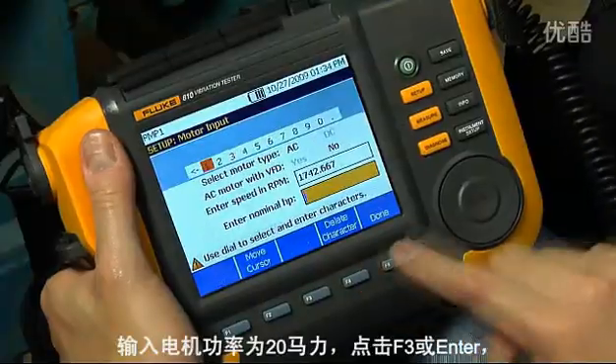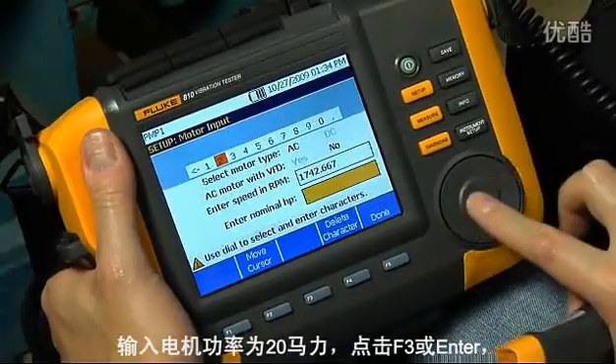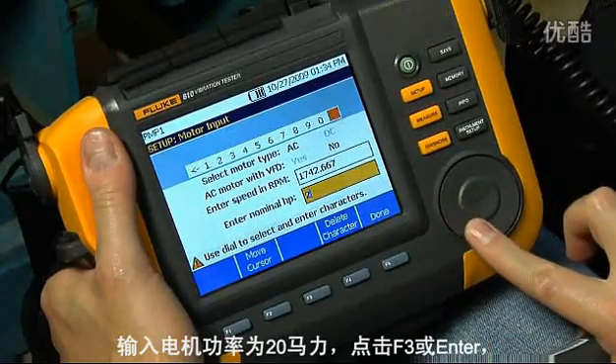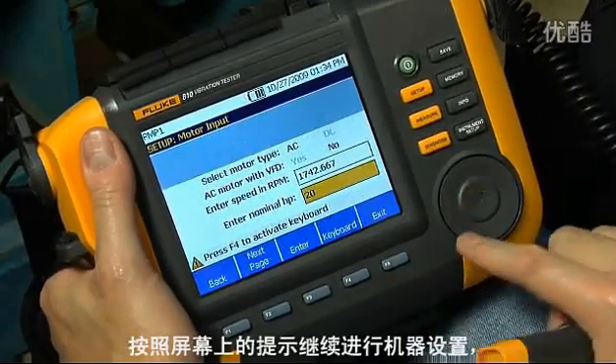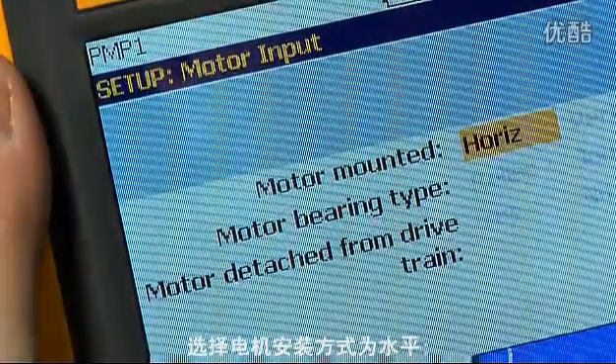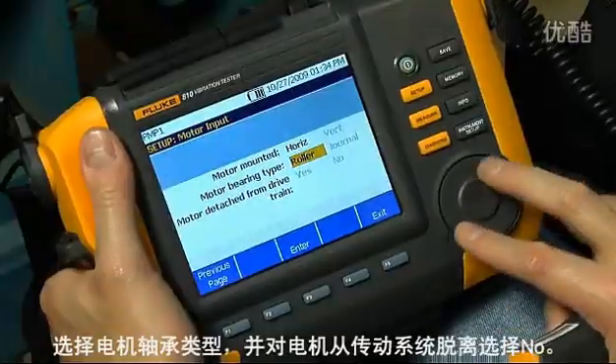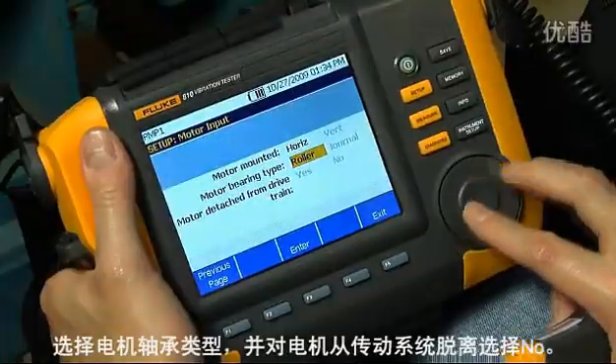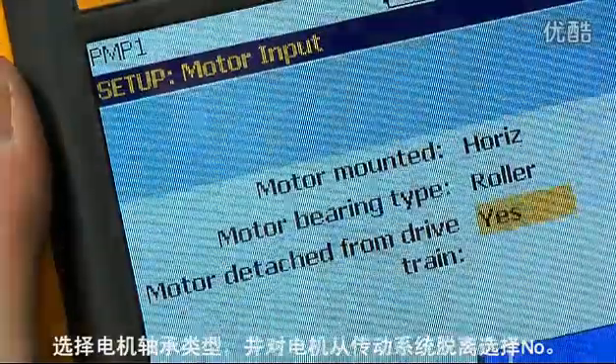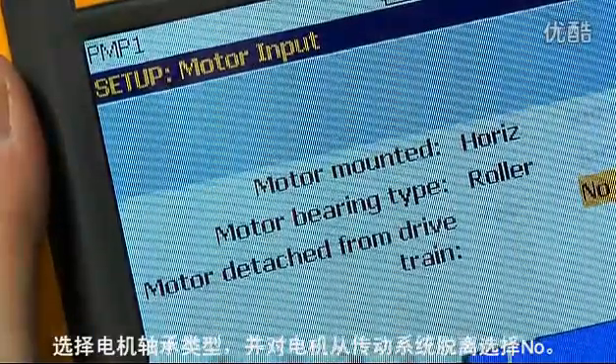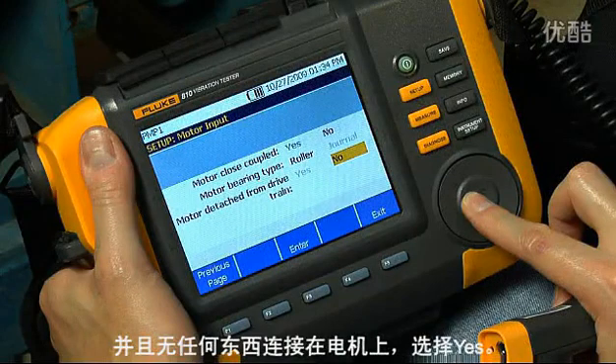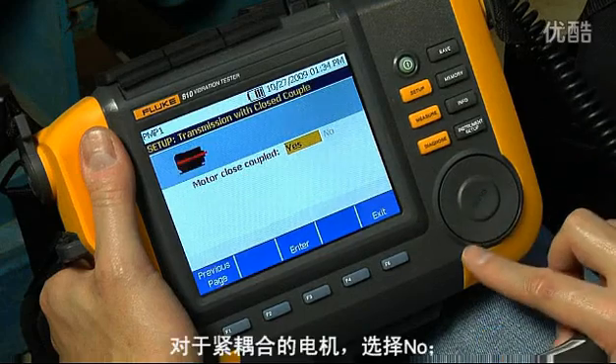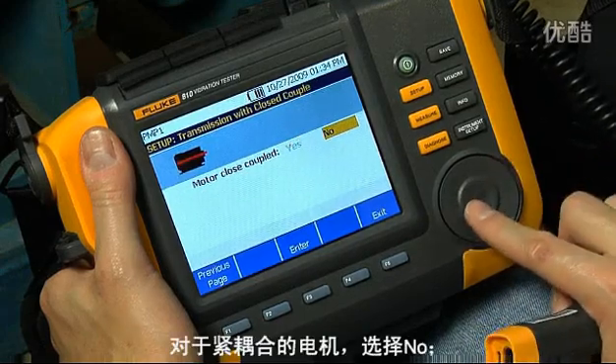Enter 20 horsepower for the motor's horsepower, then hit F3 or enter and follow the on-screen prompts to continue with machine setup. Select horizontal for motor mounting, roller for motor bearing type, and select no for motor detached from the drivetrain. If you're only testing the motor and there is nothing attached to it, select yes.